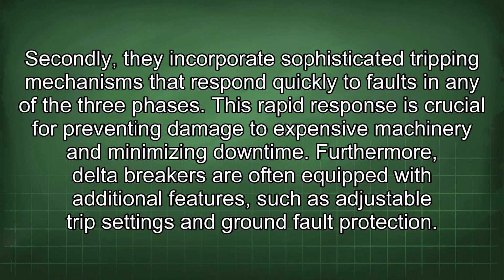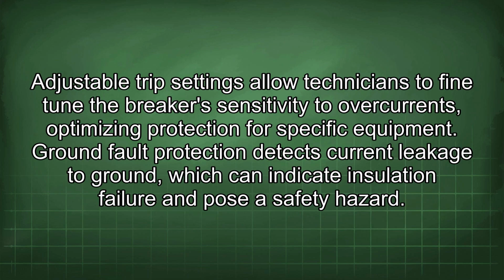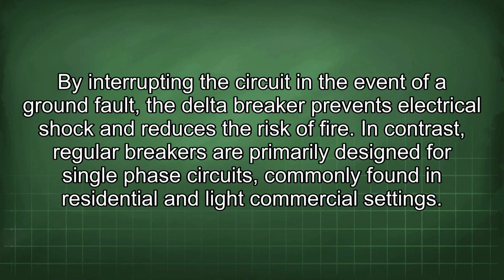Furthermore, delta breakers are often equipped with additional features, such as adjustable trip settings and ground fault protection. Adjustable trip settings allow technicians to fine-tune the breaker's sensitivity to overcurrents, optimizing protection for specific equipment. Ground fault protection detects current leakage to ground, which can indicate insulation failure and pose a safety hazard.